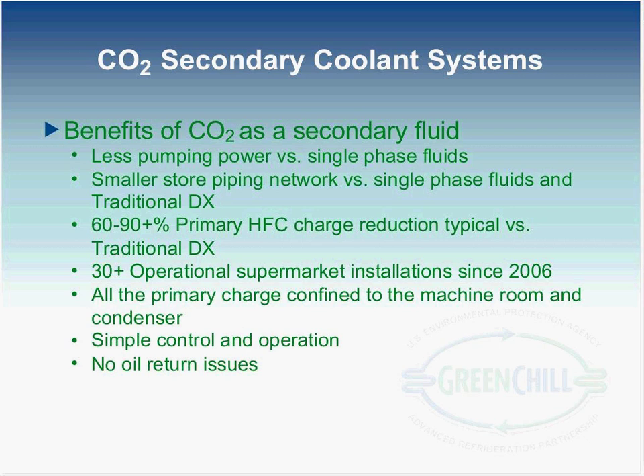So this can reduce charge and makes it easy to locate any leaks. It's just all right there in the machine room or on the roof with the air-cooled condenser. Simple system, no expansion valves and EPRs. No balancing valves. The system is self-balancing, piped and installed properly, that is. So the solenoid, you open it, like I said. Basically you have a discharge air probe in the case that senses the air and opens the solenoid. So nothing simpler than that, on-off control.